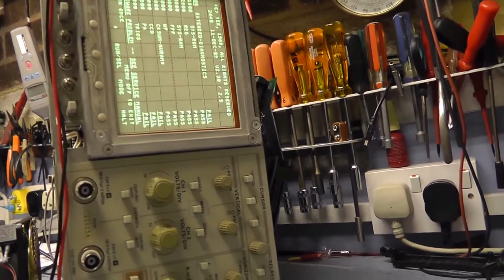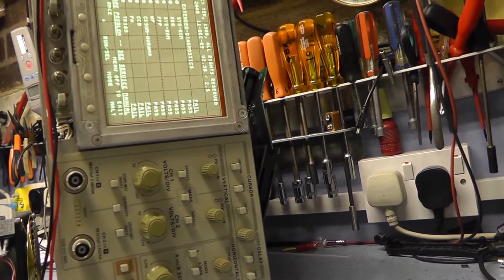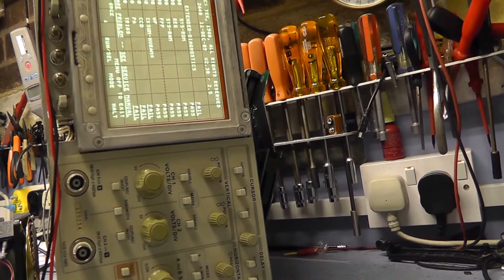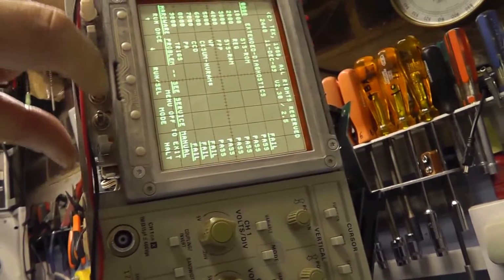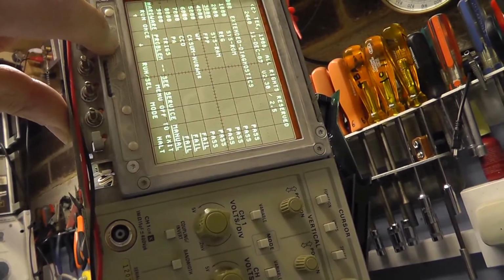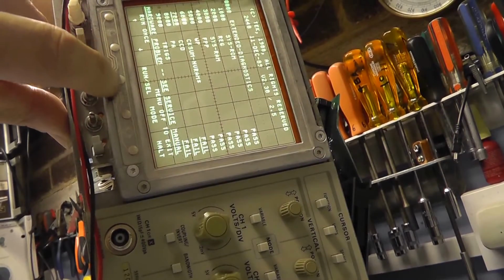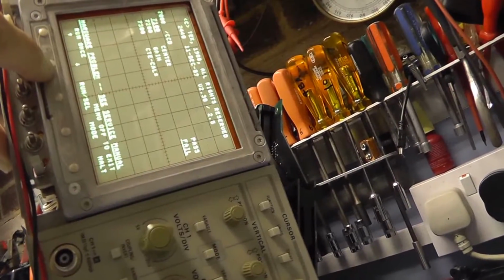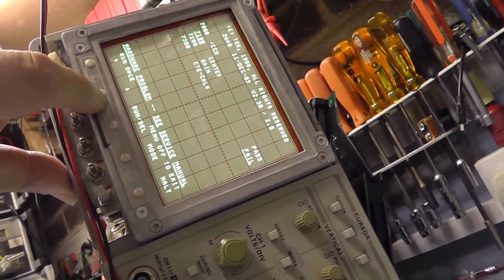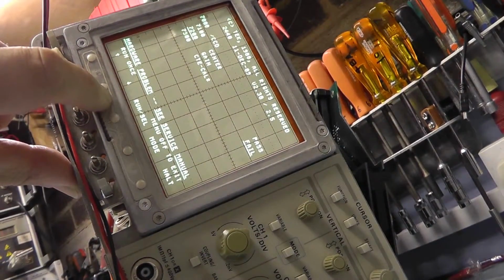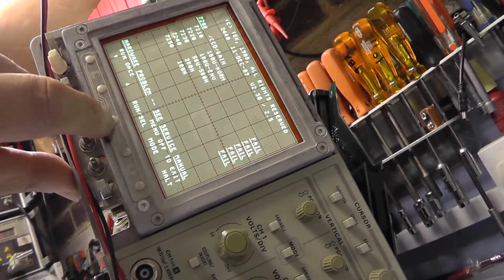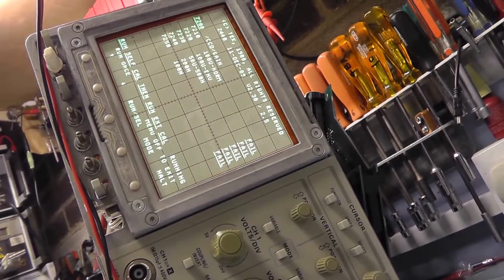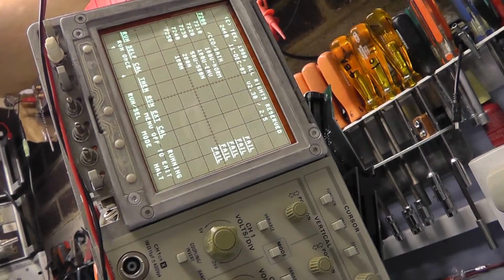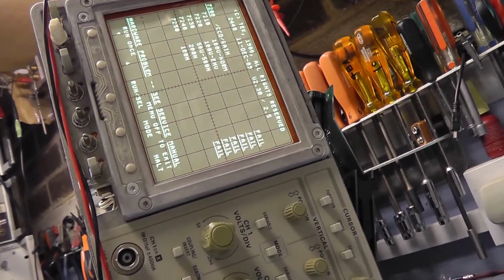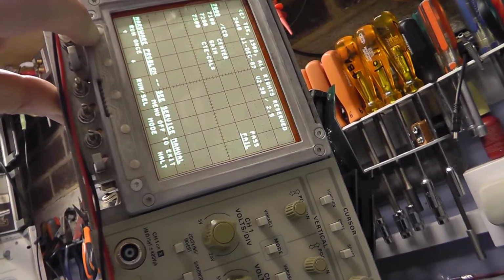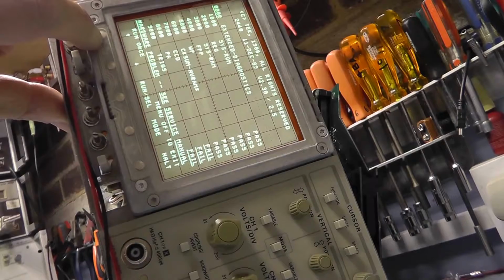Self-diagnostics passed - here we go, hardware problem. Now that's interesting. It's failed the CCD again. Let's have a look - so it's good in some ways because it means it probably isn't that processor board, I've never had that fail before. So it's the same thing, the CCD fails on the gain - when you run that, it all fails. So that still suggests the CCDs have failed. But the self-diagnostic passed, which is really odd because it's never done that before. Very confusing.